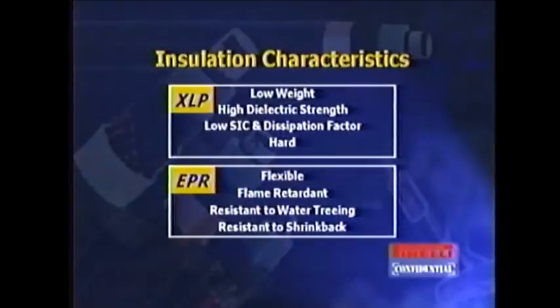This, combined with water-blocking materials at the conductor shield and also at the insulation shield, creates a very long-life cable. Some of the characteristics of cross-linked polyethylene is it's a low-weight material. It's much lighter as compared to EPR, which is another common medium-voltage insulating material. It also has a very high dielectric strength, meaning that you can raise the voltage quite high before it breaks down. Another excellent characteristic of cross-linked polyethylene and tree-retardant cross-linked polyethylene is its low SIC and dissipation factor.